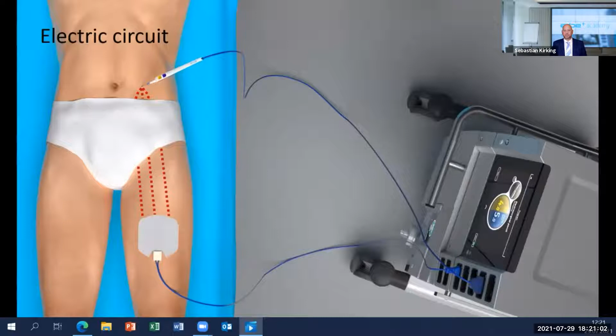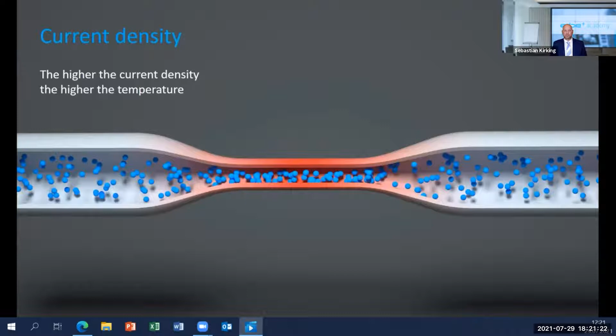This is actually determined by the current density. As you can see in this animation, the heat only develops where the charged particles are sort of squeezed through a thin constriction. This is where the current density becomes high and thereby the temperature becomes high. Note that this happens wherever there is a constriction within the electric circuit. Now, in case of a monopolar instrument, the second electrode therefore has a large contact surface to ensure that the current density remains low.